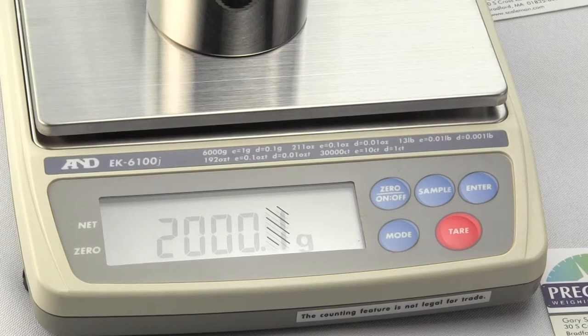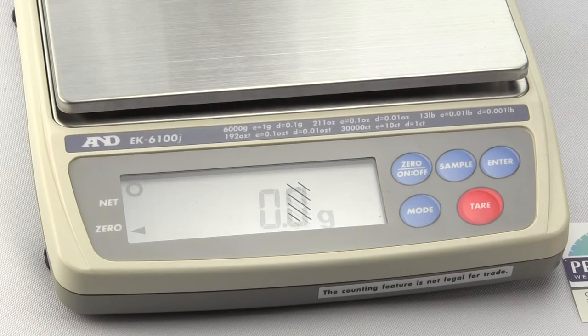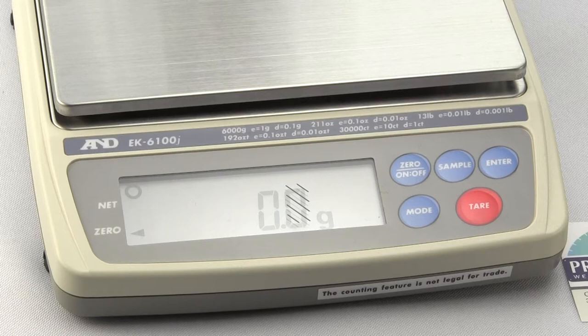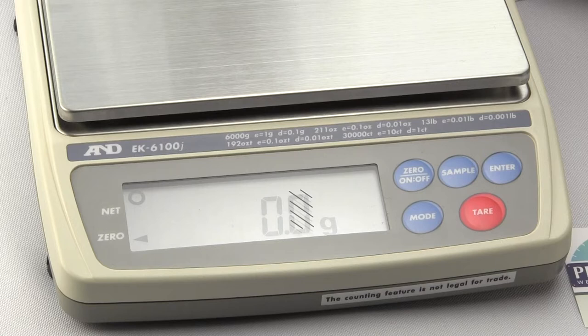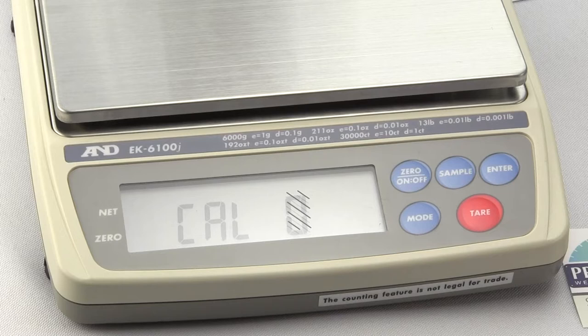Now, one of the nice things about the EKJ series is the calibration weight is user selectable. It's always best to at least calibrate with 50% of the capacity. I'd really recommend that people calibrate the scale with a 5 kg weight. But a 5 kg weight is pretty expensive. So we can go into the CAL mode and I'll show you how to change it. And we'll just say we'll use a 2 kg mass to calibrate.